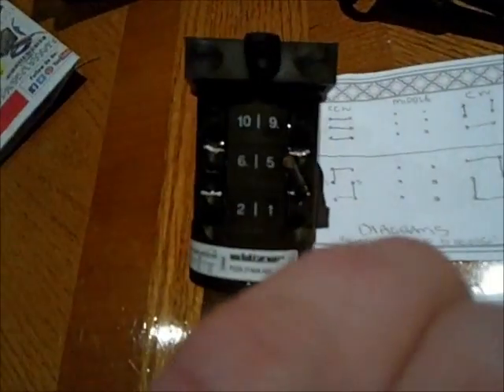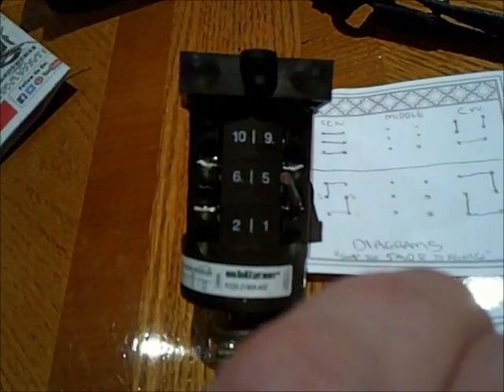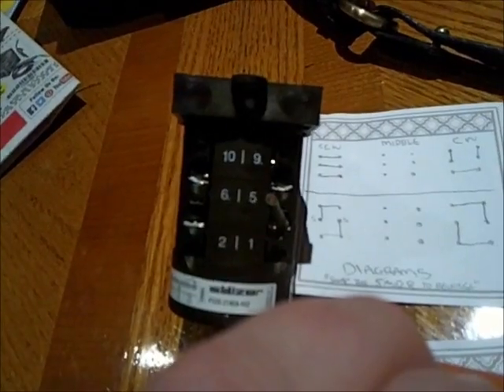And this is a P220, and there's a lot of data online, so it's kind of nice. You will see the wiring. But basically, for single pole use, you see a 3, 4, 7, 8, 11, 12 on one side, and on the other side you've got 1, 2, 5, 6, 9, 10. So there's 12 total connections. I know you have 6 wires, so you've got to figure out where this goes. Like I said, the online info is pretty good.